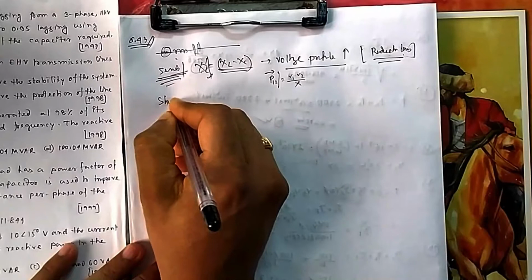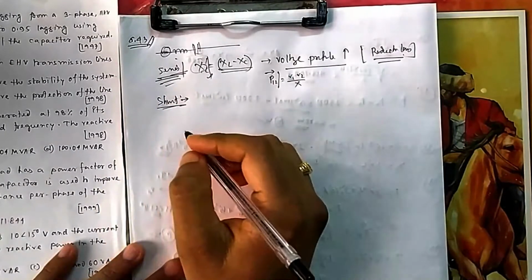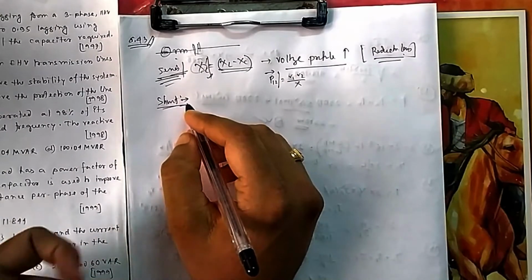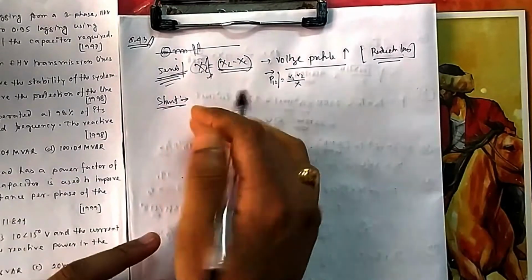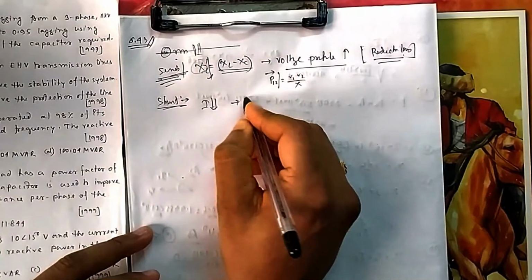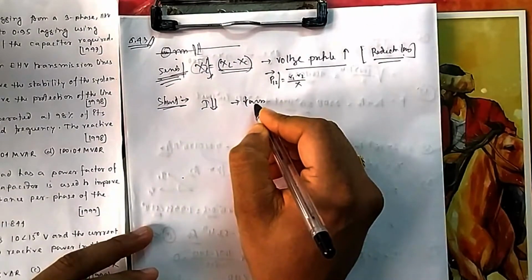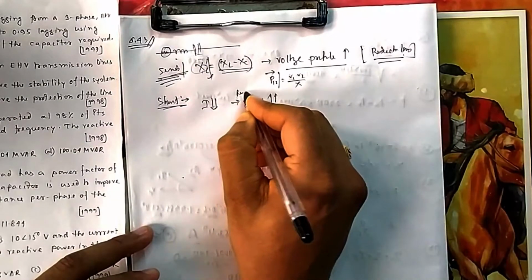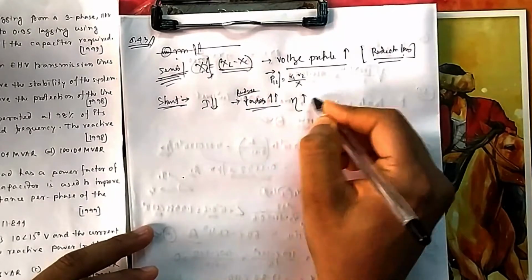But in case of shunt, you know what is the purpose of shunt connection? Shunt capacitors are used for power factor improvement, which directly improves the reactive power requirement, which improves your power factor, or you can say reduces your I. Once I gets reduced, your losses get improved very much. So the main purpose is loss reduction, or you can say improving efficiency, both.